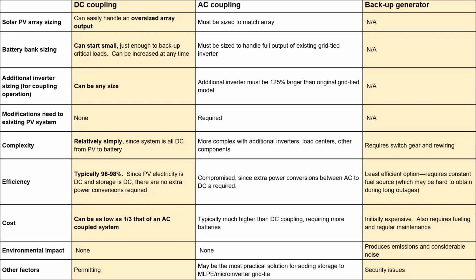The nice thing about DC coupling with respect to the array is you're traditionally using an MPPT charge controller fed from the solar panels, and the MPPT allows for some amount of oversizing beyond what your batteries can store. So you can have a much larger array to a smaller battery size ratio and still maximize the amount of time you'll achieve full production with respect to the charging needed. That also allows the battery bank itself to be smaller, whereas AC coupled systems traditionally end up with oversized battery banks—especially with lead acid, where you're only able to use 50% of the battery bank. It's a lot of investment for half of it to just sit there.